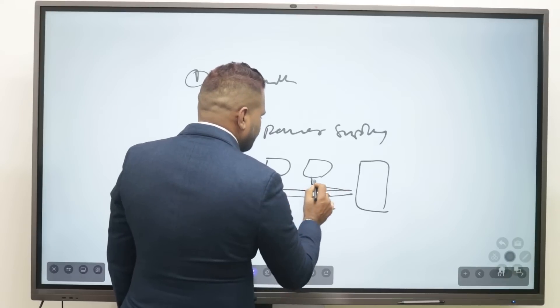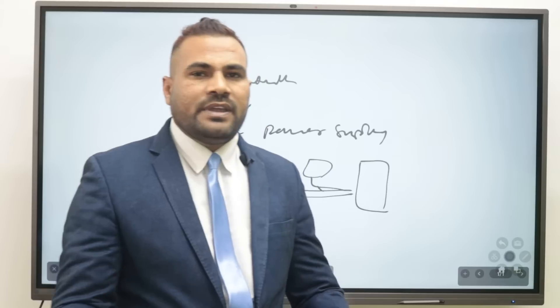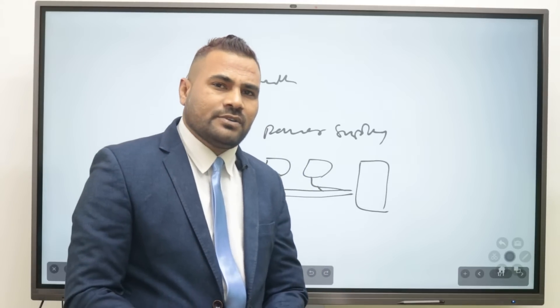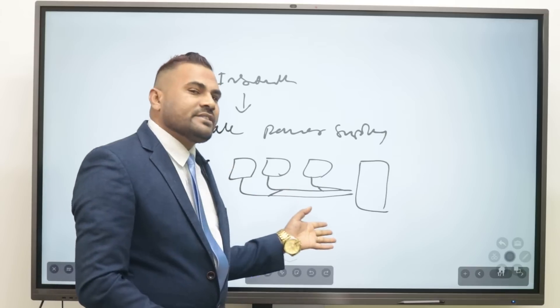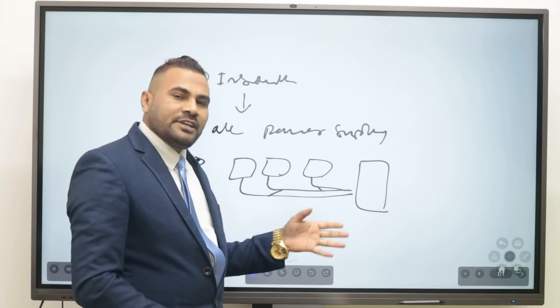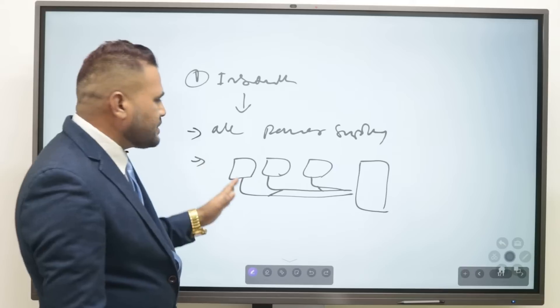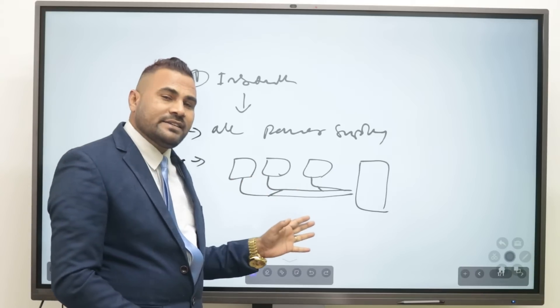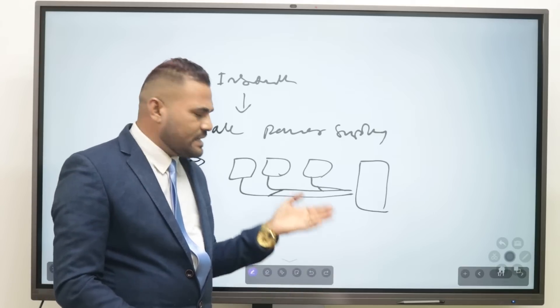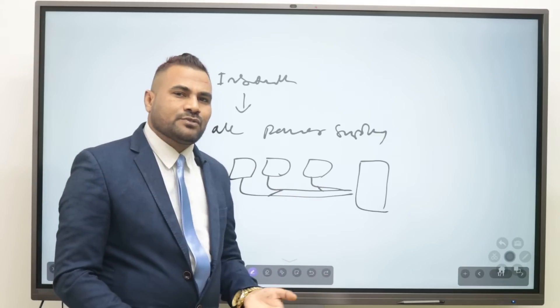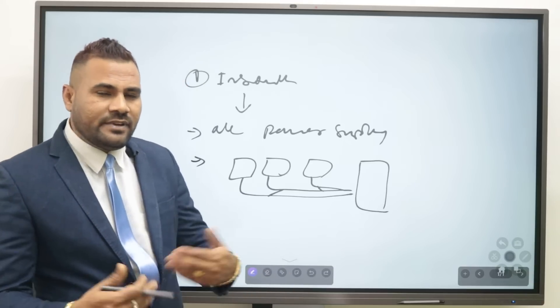How do we make the addressing, and what is the purpose of addressing? We connect each indoor unit to the outdoor unit — master to slave units. We must understand this because communication wiring is a different part from power supply wiring and thermostat wiring. For addressing, we need to know whether the system uses auto addressing or manual addressing, and we must follow the instructions in the installation manuals, with supervision from supervisors and engineers.